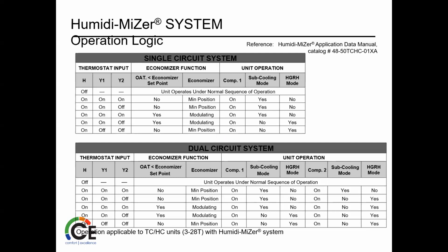So just real simple, depending on what inputs we're getting is what it tells the system to do. If we have an economizer, which you can with a Humidi-MiZer, they'll work in conjunction. So depending on what call we get or what mode it's in, it'll check: are we in subcooling mode? Is the hot gas reheat on? Yes, no. It just depends on where the inputs are and what the system needs to do. So it'll work easily with an economizer.